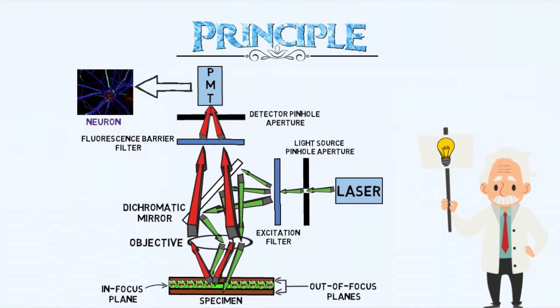Light originating from an in-focus plane freely passes the detector pinhole aperture, whereas light coming from out-of-focus planes is largely blocked by the pinhole, not letting it reach the detector. This helps create a sharp image of a specific portion of the specimen being examined. The target region of the specimen is scanned point by point, and then an image is produced pixel by pixel.